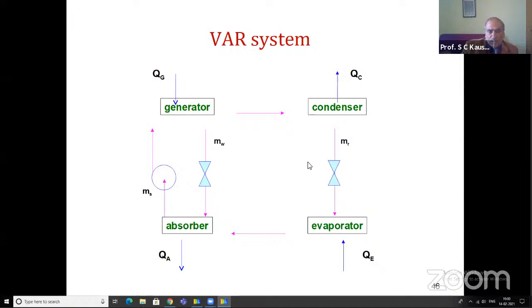This is the simple vapor absorption system. You can see the condenser, expansion valve, and evaporator. These are the same as in a vapor compression system. The mechanical compressor is replaced by this generator absorber assembly, and the purpose is to reduce the compression work. The absorbent takes up the vapor coming from the evaporator, and it is then pumped with this liquid pump to the generator heat exchanger, where input heat is supplied and refrigerant vapor is generated. This is condensed in the condenser heat exchanger, and then the condensate is passed through the expansion valve, the same process as in a vapor compression system. This is the only difference: the generator and absorber assembly is just replacing the mechanical compressor.